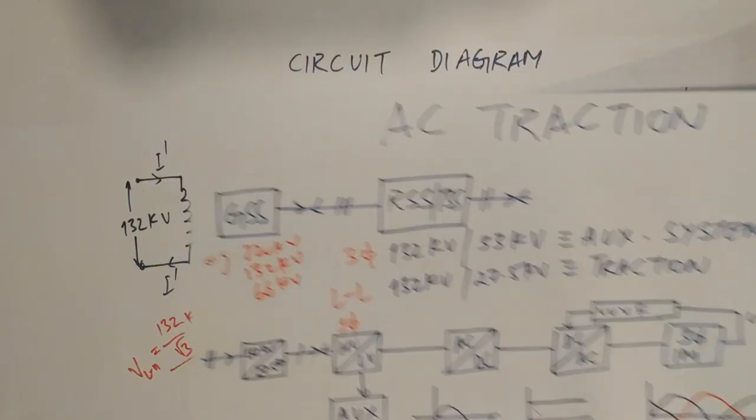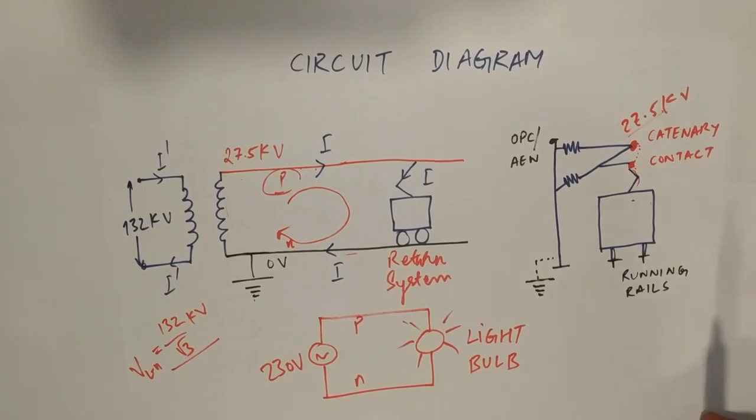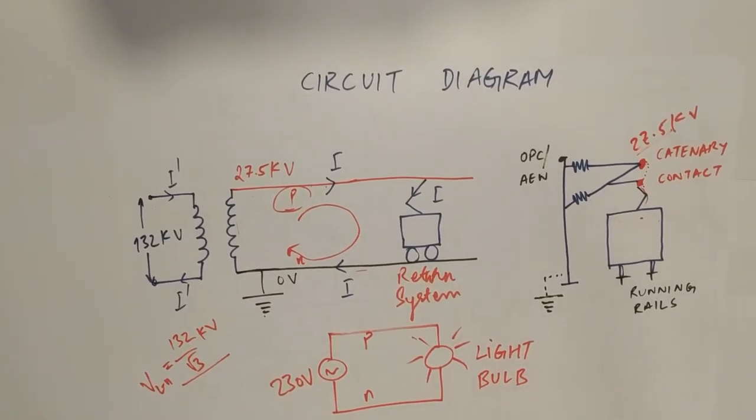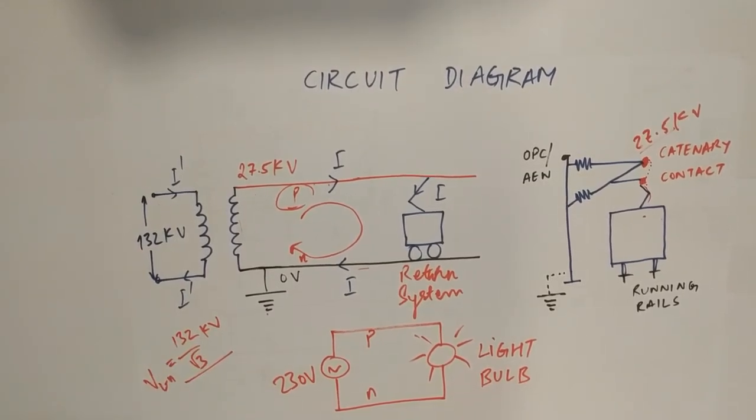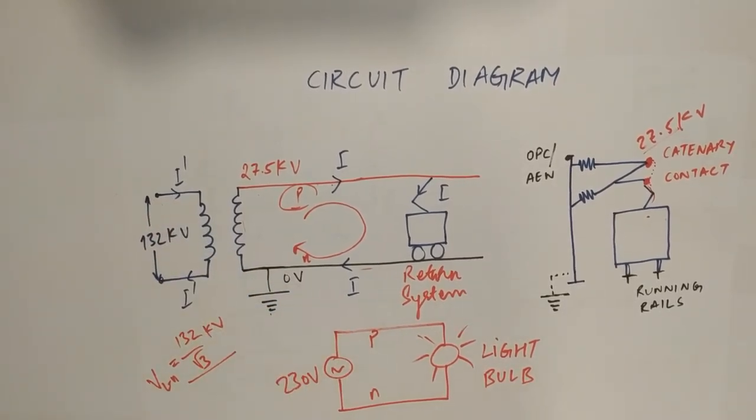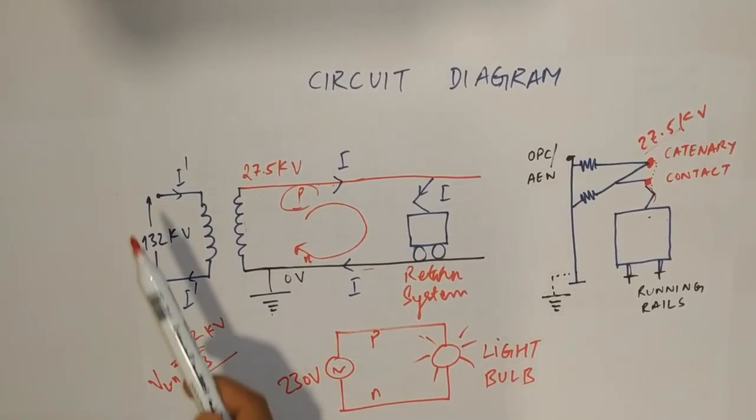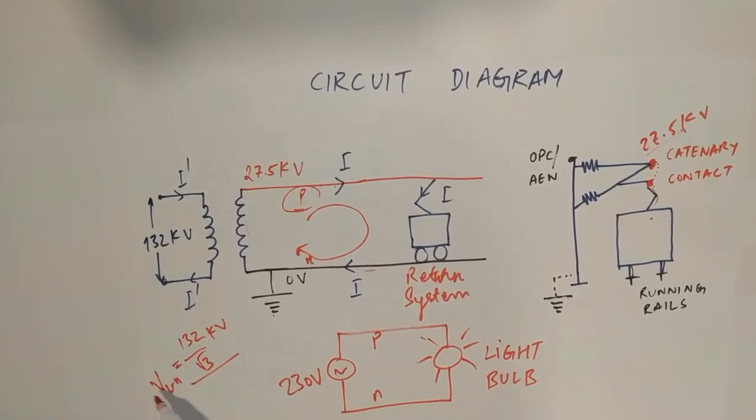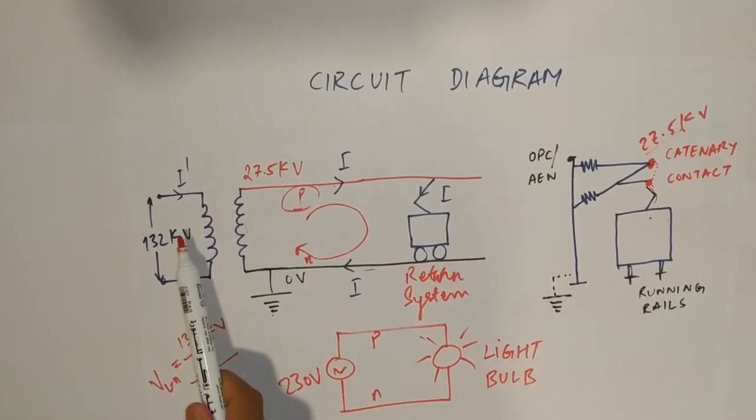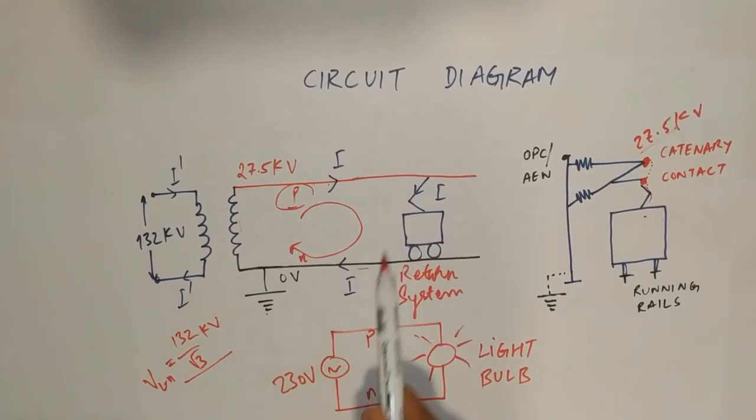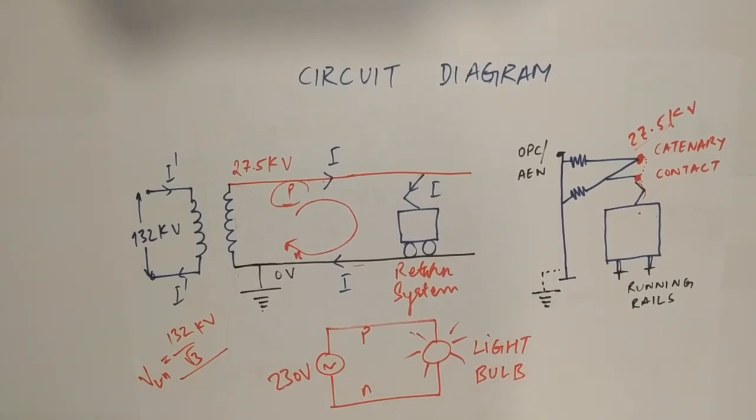Now, I will show you a simplified circuit diagram for how this system works. So, once we have got this 132 KV in the high voltage side of the transformer, this 132 KV is line to line. If someone asks you what is the line to ground voltage, then you have to show that it is 132 by root 3. This high voltage is converted into low voltage of 27.5 KV which is being fed to the overhead contact system and this is your return system.